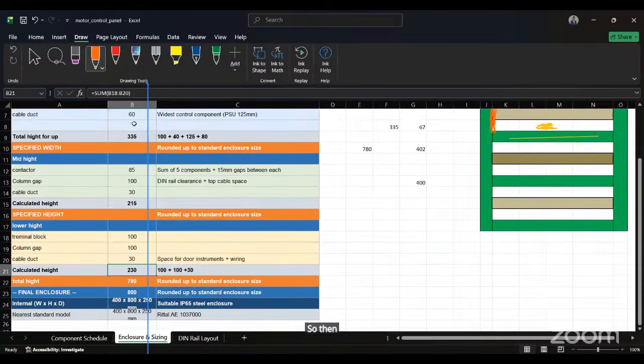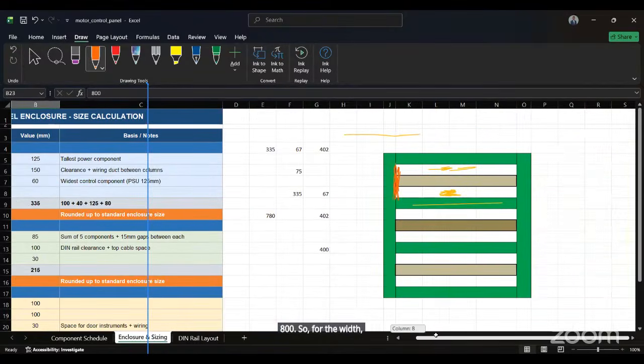So then we add this plus this plus this — that's how we get 780. The closest standard to 780, because you won't see 780 in the panel layout, is what we can see there, 760 or thereabout. I said we shouldn't round down, we should round up. So the closest to it is 800. So for the width that we were measuring before, from here...